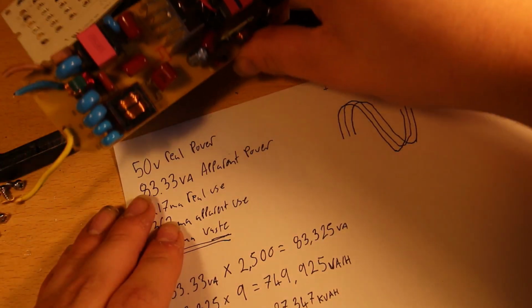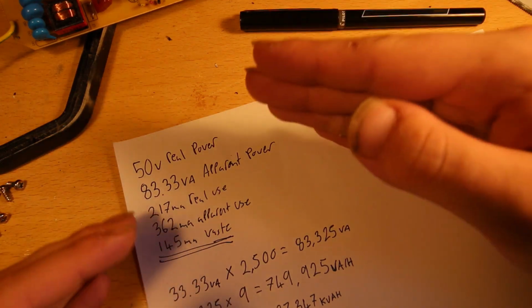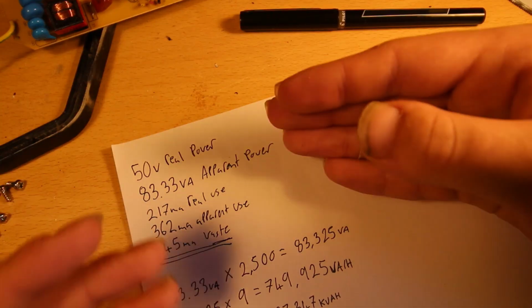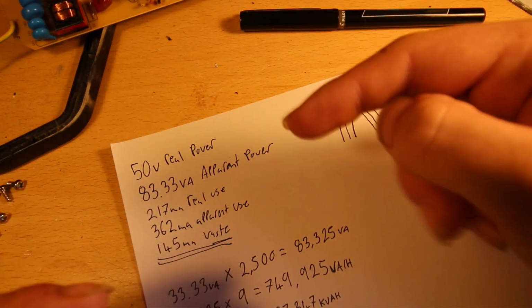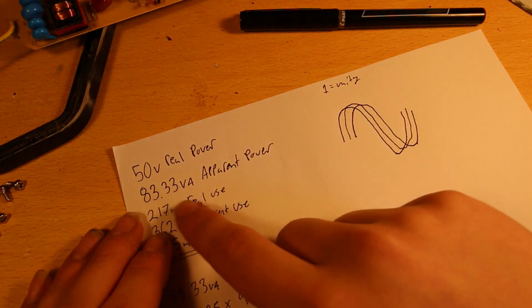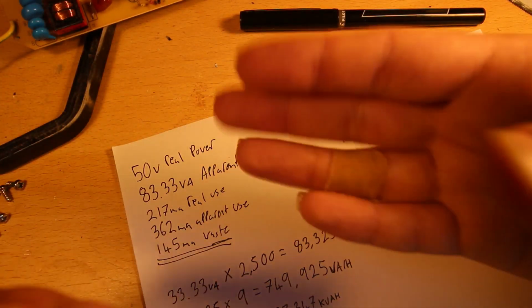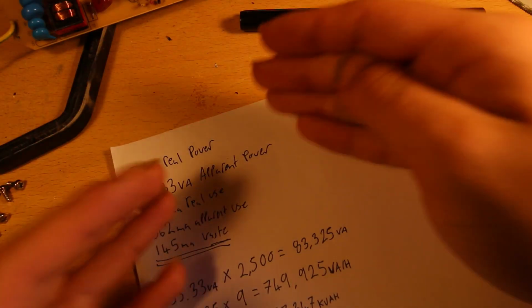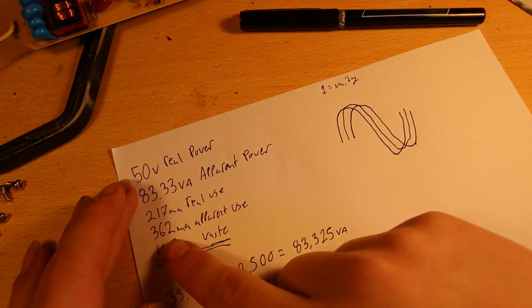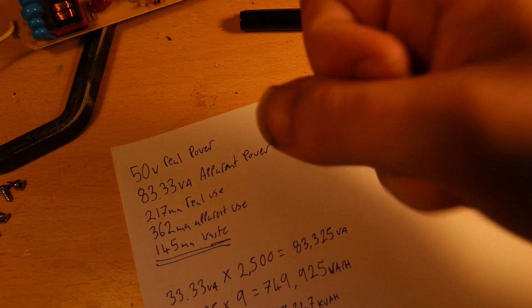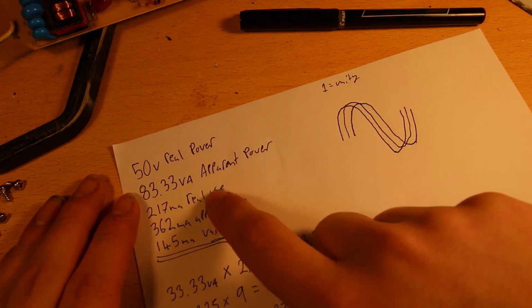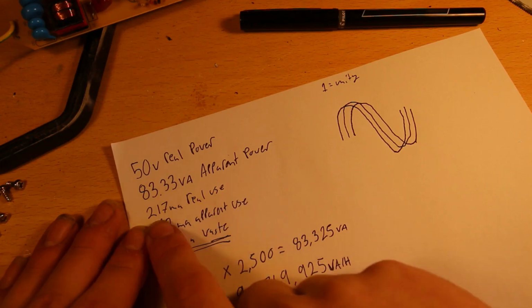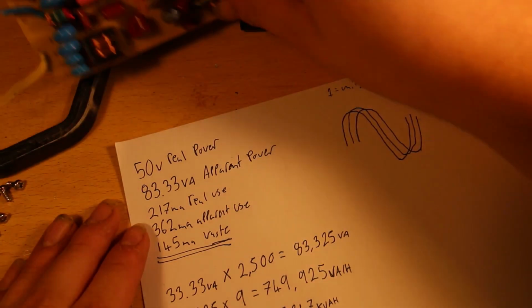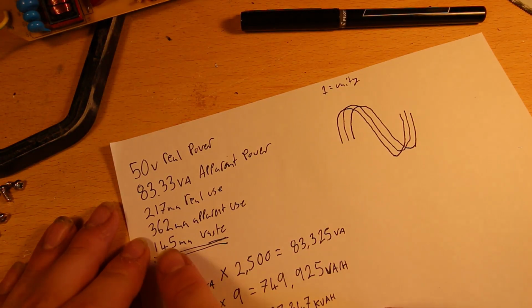So if we go over here, I'll explain what all this means. 50 watts of real power is how much this light fixture uses. If we assume it had a fairly average power factor of about 0.6, fairly normal for a switch mode supply, it would be drawing 83.33 volt amp of apparent power. So our generator has to produce 83.33 volt amp of power. We have to transmit 362 milliamps of actual current down the wire, where we only need 217 if we were to have a power factor corrected board like this. So we're saving 145 milliamps of basically wasted current per fixture.